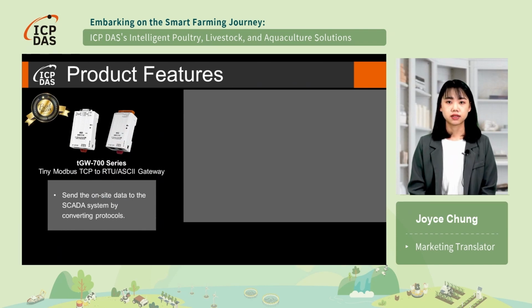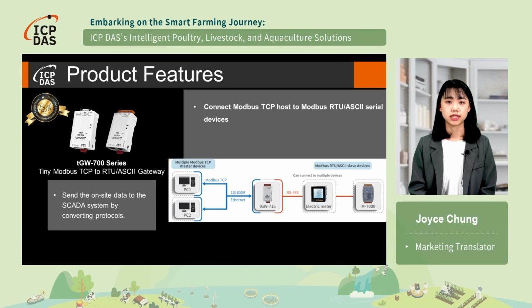In this case, ICP DAS TGW700 series Tiny Modbus TCP to RTU ASCII gateway takes the on-site data in Modbus RTU protocol and sends it to the SCADA system using Modbus TCP protocol. The TGW700 series Tiny gateways can bridge the gap between your Modbus TCP system and your Modbus RTU ASCII serial devices, meanwhile eliminating the cable length limitations of traditional serial communication equipment, so you're not confined by cable length anymore.